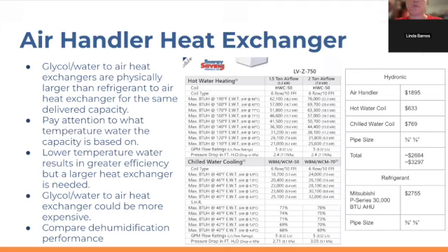And so, what some hydronic air handler manufacturers have done is that they recommend that in places that have a significantly different heating load versus cooling load, such as in the northern states where you get a really big heating load, but then the cooling load's not that bad, but there's still humidity in the summer to manage, that you have an air handler with two coils. So in the heating season you can have your chilled water coil running hot water on top of your hot water coil, and the two combined will deliver enough heating capacity to the home to stay warm in the coldest days of winter. But then in the summertime, when you need that dehumidification, you can have only the chilled water coil running, and then not overcool the building, but still allow that chilled water coil to stay pretty cold to be able to get dehumidification effects.